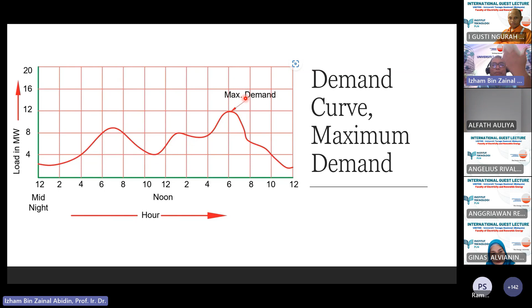Okay, so we need to have the demand curve, and every demand curve must have what you call the maximum demand. That means the maximum power that the load requires for a particular time. Based upon that, there are certain factors that you can derive. This one here is called the demand factor. The demand factor is the maximum demand, which is the peak demand for the day, divided by the total connected demand. Maybe the maximum demand for the day is 50 megawatt, but my total connected load is 100 megawatt. Therefore, the demand factor will be 50%.